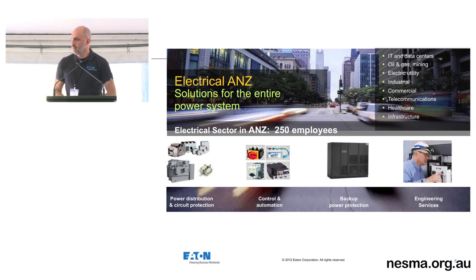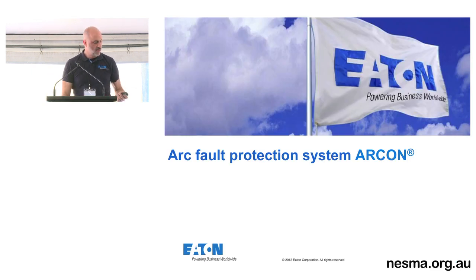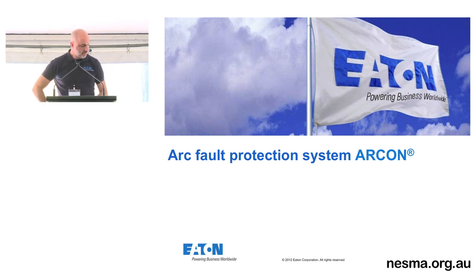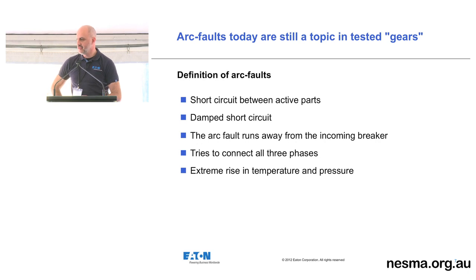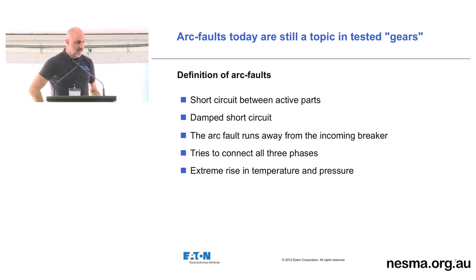All right, without further ado, we're going to go on to our arc quenching system. The system we've got is called ARCON. Obviously, safety is a major issue with switchboards. A lot of switchboard builders are required to have arc fault containment testing in whatever they build, through various methods. And look, we'll just start with the definition of an arc fault. Obviously, it's a short circuit between active parts. The result of an arc flash is the serious part of this.